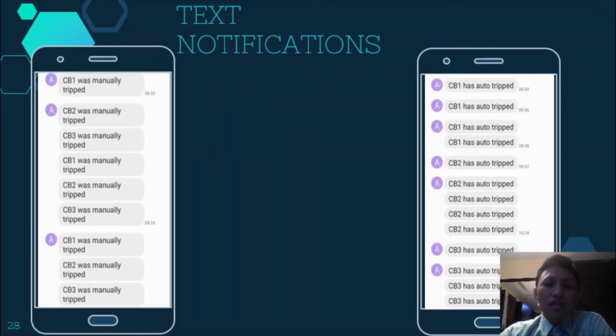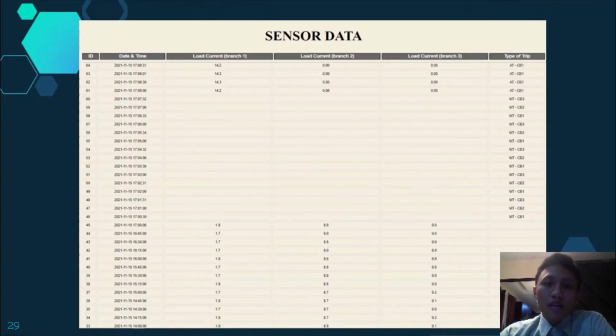These are the actual text messages sent by the system when a manual trip or automatic trip has occurred. A web page is also created to store the data gathered. This is where the system uploads the load current of each branch. It is taken every 15 minutes. It also contains the type of trip that occurred in the circuit breaker and which among the circuit breakers have tripped.